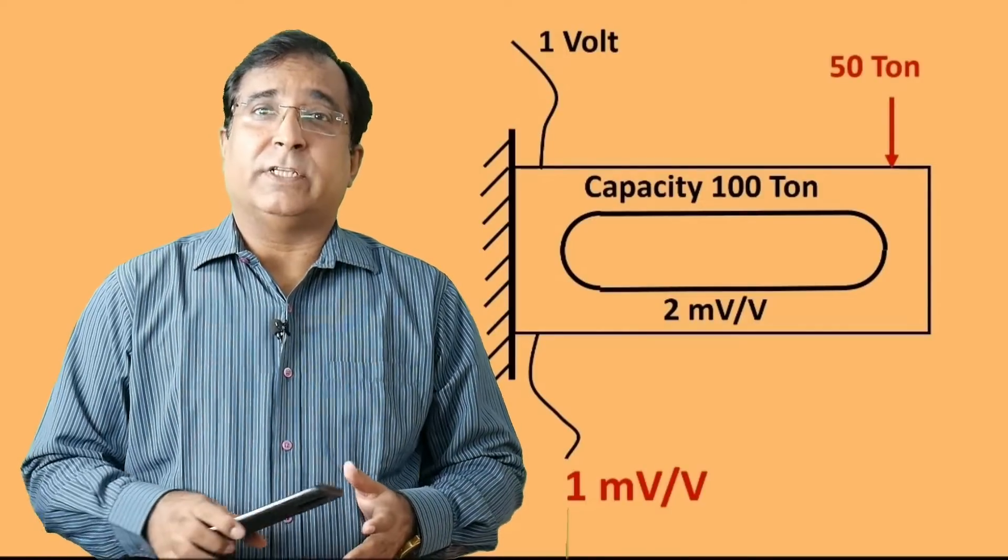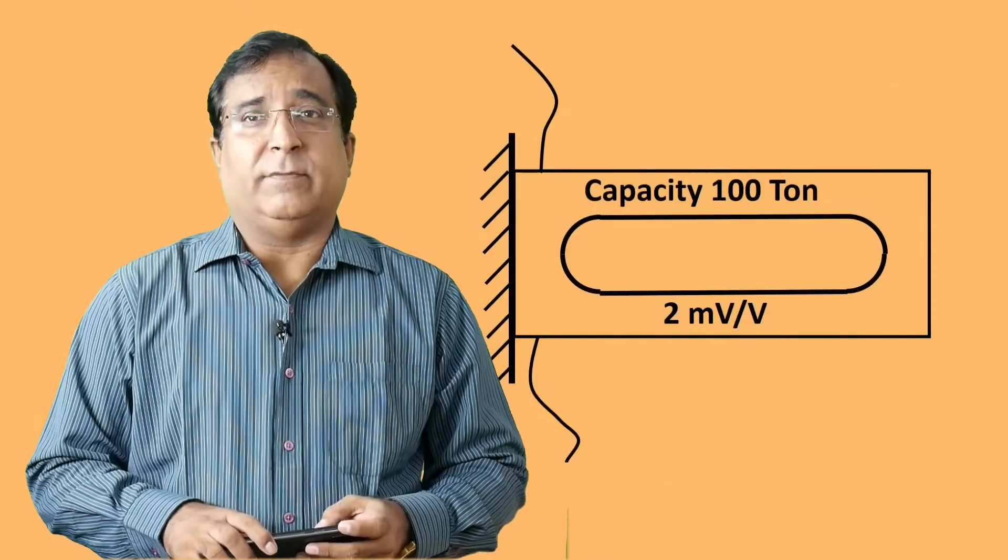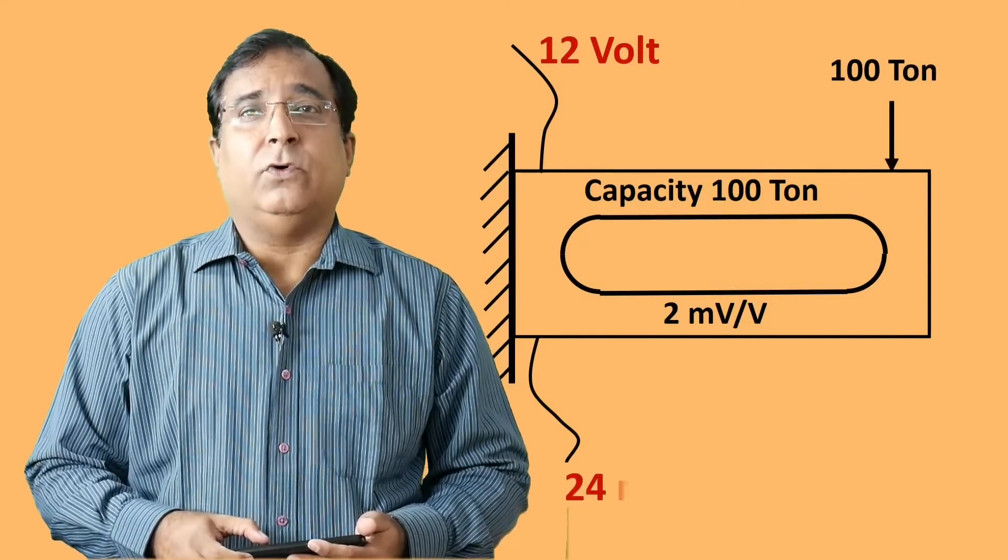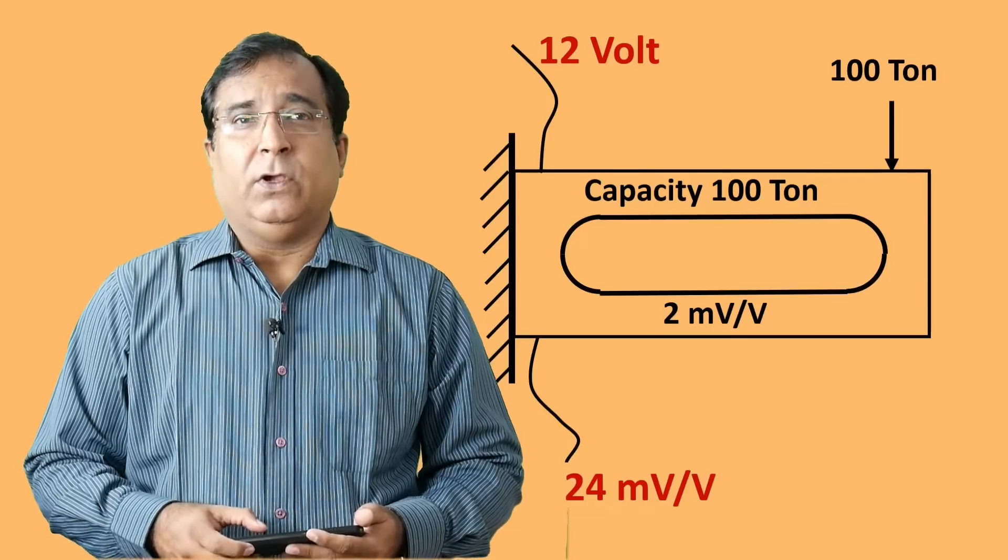But here the excitation voltage is mostly given at 12 volt instead of 1 volt. Now my output at 100 ton will increase to 24 millivolt. So it will be good for measuring circuit to measure this higher output and makes measurement easy.